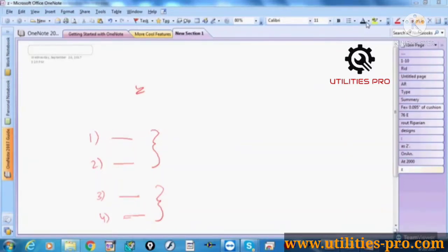So as a mechanical, you cannot decide that alone. So there is involvement of the interior, architect, and client. Why the client? Because the client is going to invest. For example, if you suggest a chilled water system, the initial cost is high, but no doubt the running cost is less. So if the client is not able to bear that initial cost, we can go for the VRF system. Okay, so we have these options, and after learning chapter 5 you will be able to handle this. So I think you got the idea of what a concept drawing is, right?